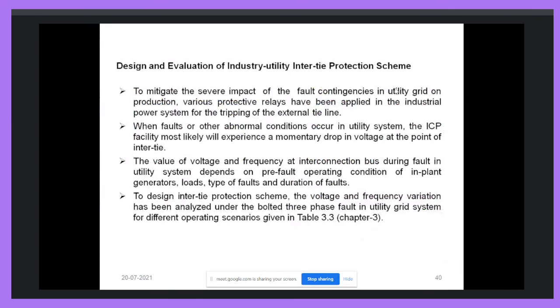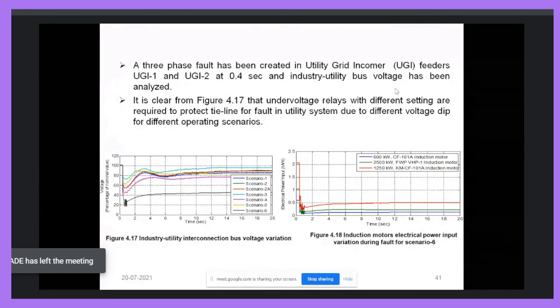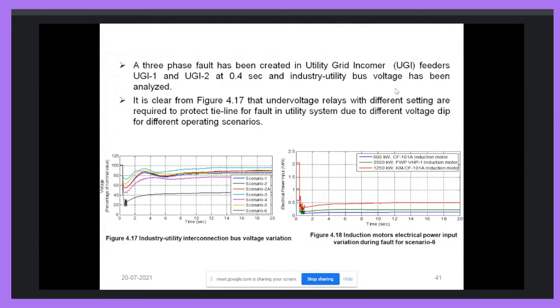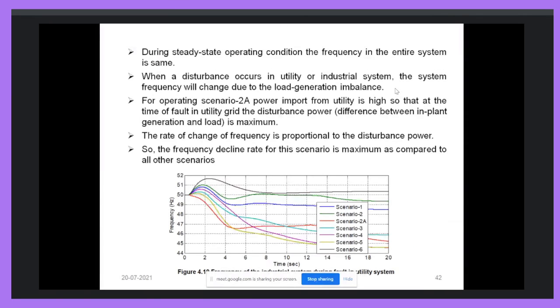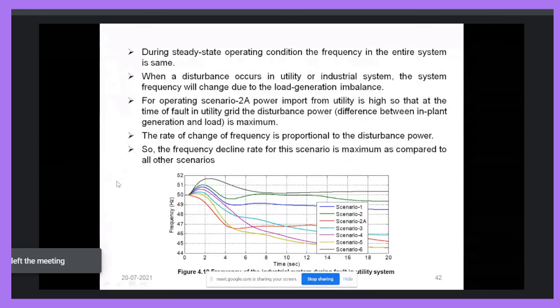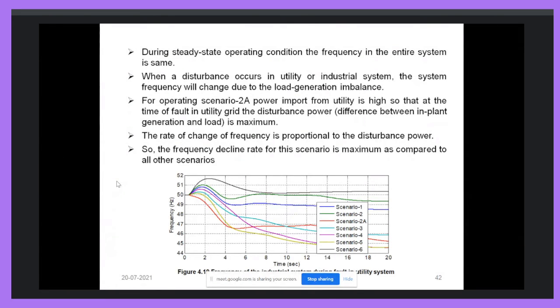Now here we can see the frequency of the system. Utility-industry interconnected bus voltage we can see, and correspondingly the variation of the output of the induction motor. Now here you can see the variation of the frequency for the different operating scenarios when the utility grid is disconnected. It is not the same for all the cases. All these cases have different amounts of load generation mismatch, so for different load and generation mismatch, the frequency variation will be different. But in case of the conventional load shedding technique, they will not understand what the operating scenario is. They will not consider the present operating condition.